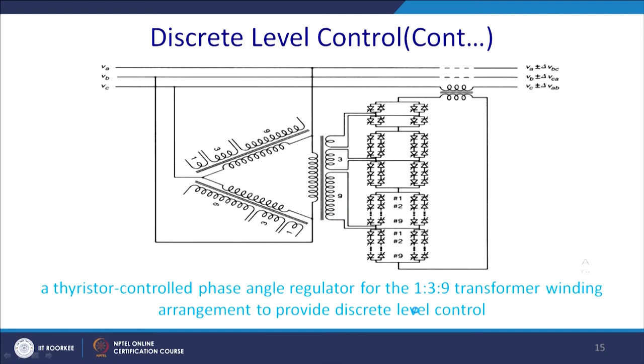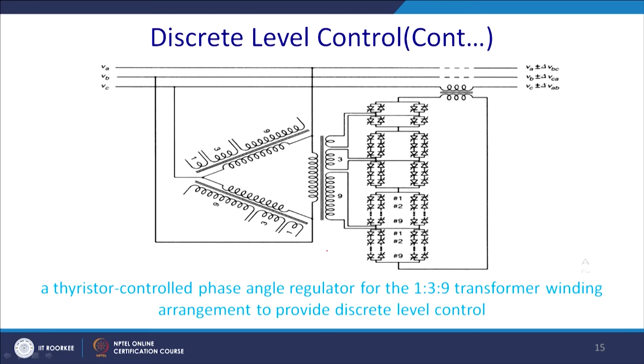Similarly, the thyristor control phase angle regulator, where you have to inject the voltage in quadrature. We have already seen that if you want to inject 90 degrees with phase A, we have to apply the voltage BC. So, this kind of arrangement gives you the quadrature phase angle; only one phase has been shown. So, this is with the A and this is the B and the C. The delta will give you the 30 degree phase shift. A particular vector group has been chosen, basically Dy1, delta star 11 or 1.